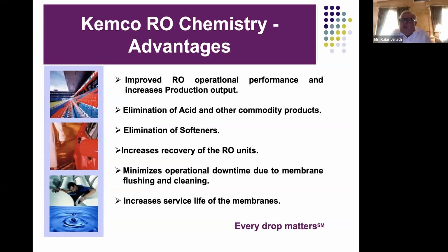Needless to say, the more we clean membranes, the more the harsher cleaning chemicals damage their performance. Every time a membrane is cleaned, the response is good, but it declines each time, and performance degrades over time until replacement is needed. So the benefit of a good chemical approach is to enhance membrane life with practices suitable for the membrane, including 24-hour operation, avoidance of cleaning, and elimination of acid, since acid adds sulfates to the water quality going to the RO.